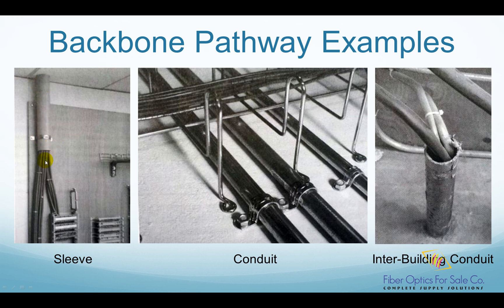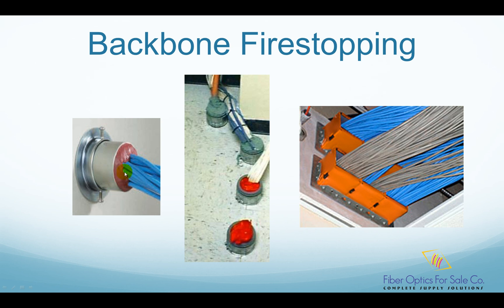Sleeves are sections of conduit that connect vertically aligned closets in a multi-story building. Metal conduits are installed as a direct run between two telecom rooms or between a telecom room and an equipment room. An underground pathway is a metal conduit run between two buildings. Backbone cables installed in a sleeve or in a slot must be properly fire-stopped after the cables are in place. Fire-stopping creates a fire-rated barrier that prevents both fire and smoke from spreading between floors in the event of a fire, using specialty fire-rated materials installed into penetrations.